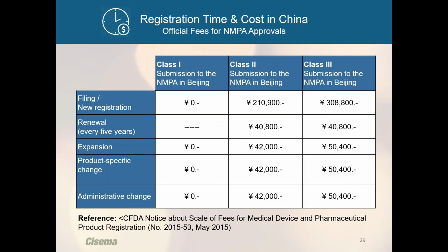When hiring a service provider for assistance with the registration, make sure the offer is a true full cost calculation to avoid unpleasant surprises. What you see on the slide is only the application fee. A full cost calculation should include the effort invested for collecting the registration file, drafting the PTR, the confirmation of the sample list, and doing the customs clearance and the transportation within China, the test fees and the supervision of tests, and all this, or if there's a clinical trial necessary.